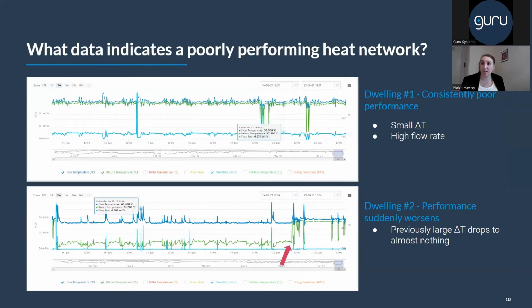Here you can see a system that is not performing very well. So again, you have your flow temperature in dark blue, your return temperature in green, and the load in the light blue. And here you can see that the flow and return temperature, the dark blue and the green, are basically running together. There is no difference in temperature or delta T between the two. If you don't have a large delta T, then your system is not running efficiently, and this will cause you problems such as high costs of running and also no carbon savings.